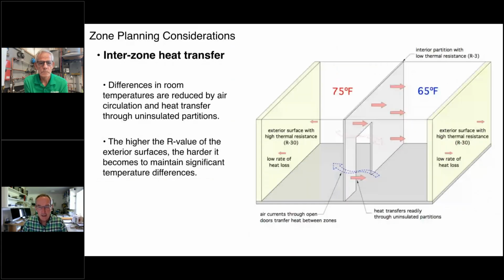Here's another consideration. We call it interzone heat transfer. Just imagine that we've got a building envelope, and today energy codes require fairly high thermal resistance. So those two yellow walls I'm showing are R-30. And then somewhere in between, we've got an uninsulated partition, and we have an open door between those two rooms. And the combination of the low thermal resistance of that partition, as well as the free air movement between those rooms through the open door, it's hard to maintain a significant temperature difference between those. And I'm showing 75 and 65. That would be very difficult to maintain.